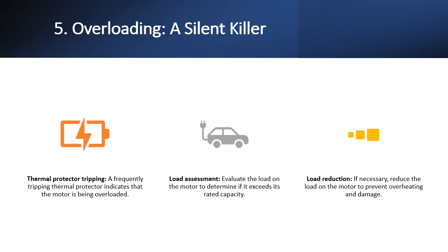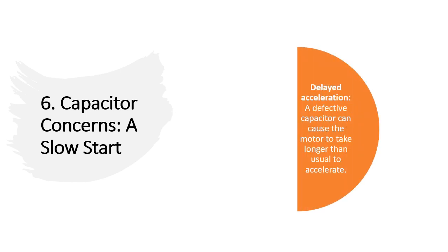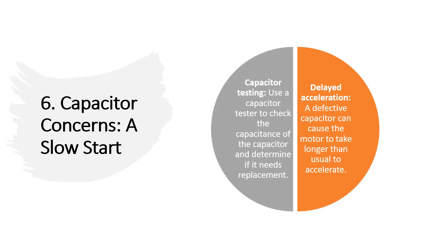6. Capacitor concerns, a slow start. Delayed acceleration: a defective capacitor can cause the motor to take longer than usual to accelerate. Capacitor testing: use a capacitor tester to check the capacitance of the capacitor and determine if it needs replacement.